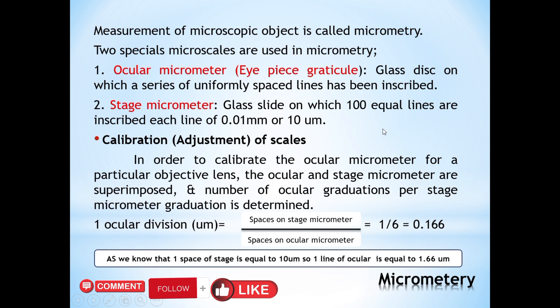The stage micrometer is placed on the stage of the microscope. It is a glass slide on which 100 equal lines are inscribed, with each line spacing equal to 0.01 mm or 10 micrometers. An important method for calculation is calibration, which is the adjustment of scale.